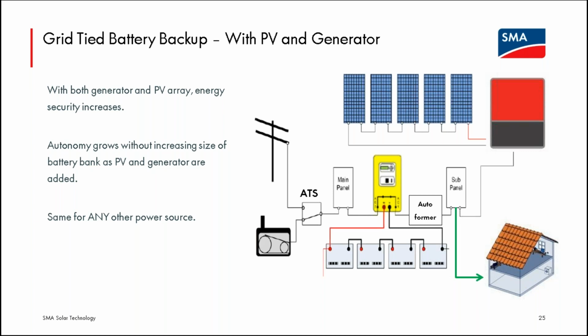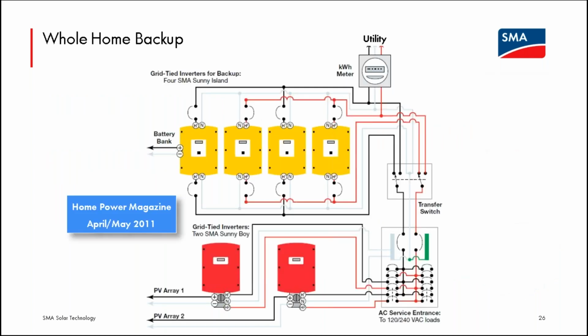And again, in this scenario, that digital input to the Sunny Island does need to be wired to tell the Sunny Island when the AC2 source goes from grid to generator. It actually opens up some frequency and voltage parameters, and prevents backfeed in the case of the generator. So it does some important things. And there is a tech note explaining how to wire that, available off the product page, and we can provide it to everyone who's in attendance.